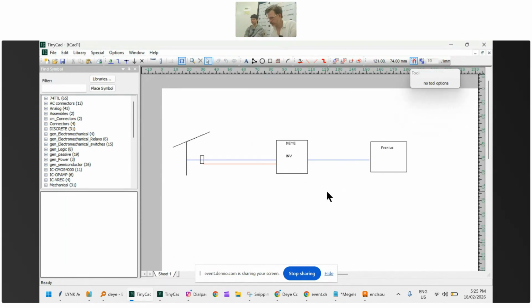In this scenario, when the grid is up, we're connected to the grid. The Deye inverter is synchronized to the grid, so it can't frequency throttle. That means the Fronius is just going to do its job of putting out as much power as it can, and it's going to go into the Deye, and the Deye is going to use that to charge the batteries. Then any excess is just going to keep flowing through the AC bus out to the grid, if there are no export limitations to worry about.